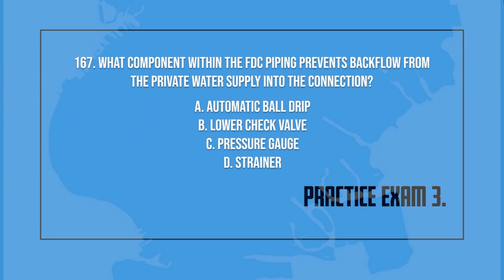(167) What component within the FDC piping prevents backflow from the private water supply into the connection? A. Automatic ball drip. B. Lower check valve. C. Pressure gauge. D. Strainer.